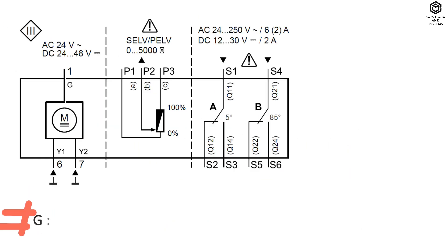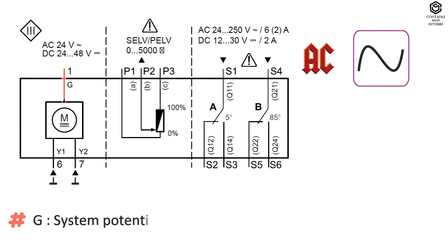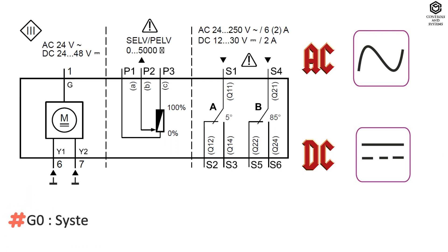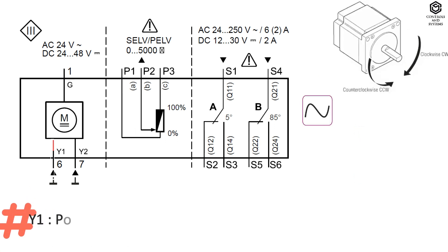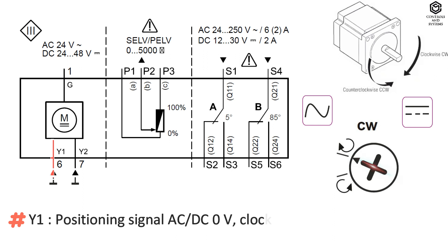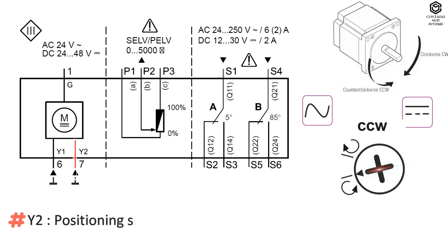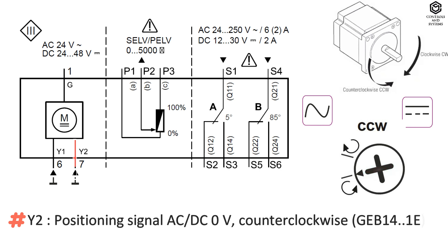Connection terminals: terminal G is operating voltage AC 24 volt or DC 24 to 48 volt supply, wire color red. Terminal G0 is neutral, wire color black. Terminal Y1 is positioning signal AC or DC 0 volt clockwise, wire color violet. Terminal Y2 is positioning signal AC or DC 0 volt counterclockwise, wire color orange.